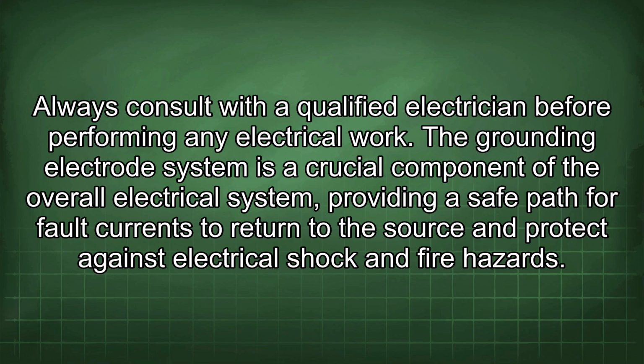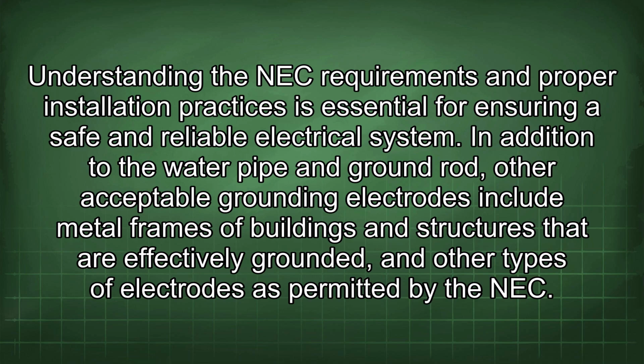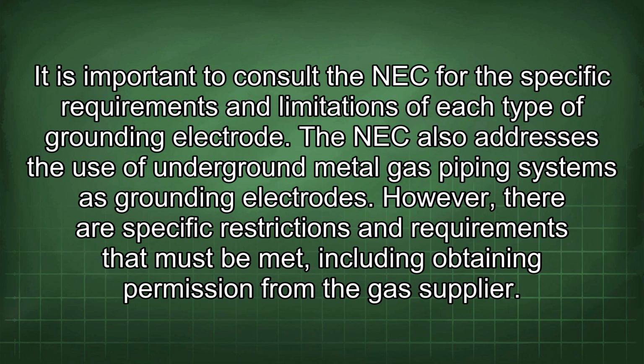The grounding electrode system is a crucial component of the overall electrical system, providing a safe path for fault currents to return to the source and protect against electrical shock and fire hazards. Understanding the NEC requirements and proper installation practices is essential for ensuring a safe and reliable electrical system. In addition to the water pipe and ground rod, other acceptable grounding electrodes include metal frames of buildings and structures that are effectively grounded, and other types of electrodes as permitted by the NEC. It is important to consult the NEC for the specific requirements and limitations of each type of grounding electrode.